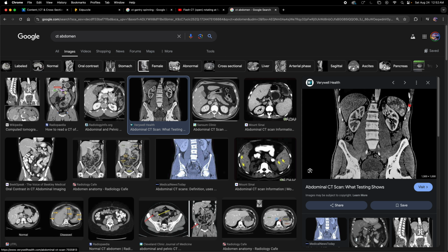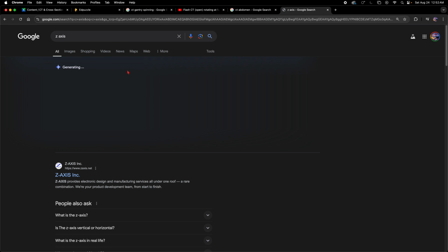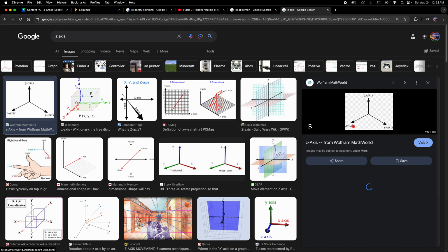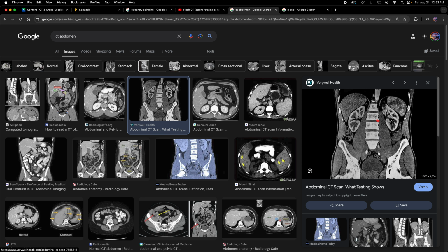And that will just adjust along the length of the patient, the Z-axis, we call it, right? So we have X, Y, and Z. The Z-axis is along the length of the patient. So along the length of the patient, the Z-axis, it would just adjust. Depending on the thickness of the body part, the machine would make adjustments.